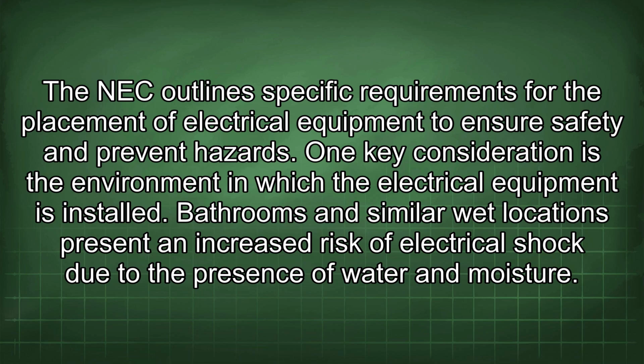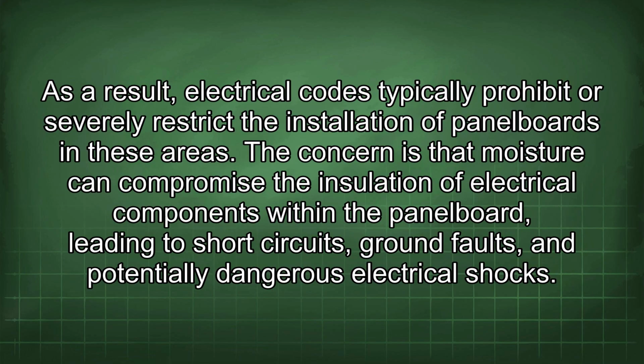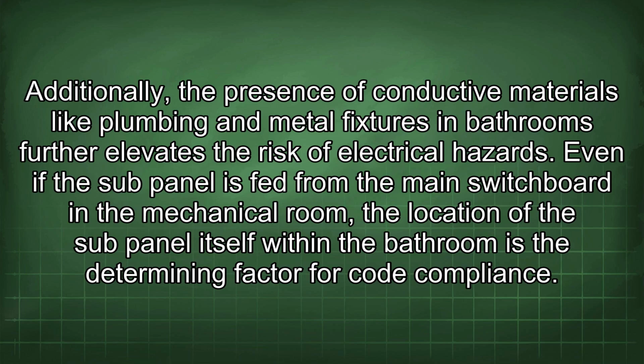One key consideration is the environment in which the electrical equipment is installed. Bathrooms and similar wet locations present an increased risk of electrical shock due to the presence of water and moisture. As a result, electrical codes typically prohibit or severely restrict the installation of panel boards in these areas. The concern is that moisture can compromise the insulation of electrical components within the panel board, leading to short circuits, ground faults, and potentially dangerous electrical shocks. Additionally, the presence of conductive materials like plumbing and metal fixtures in bathrooms further elevates the risk of electrical hazard.